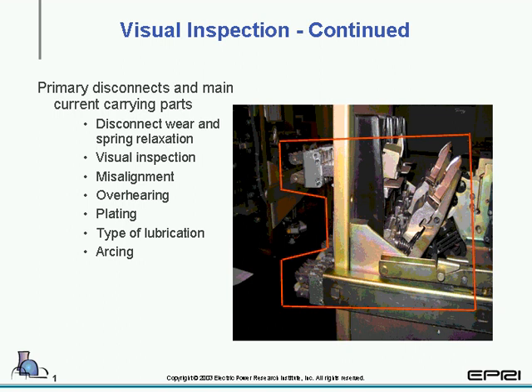So next we're going to take a look at primary disconnects and main current carrying parts. We're going to be looking at this later on as well. But when you're doing your preventative maintenance, what you're looking for is the list shown. Some of the most common are overheating and plating loss. Also, the condition of the contacts, and we'll be talking about that later as well. But as a general rule, these are some of the items you're going to want to do with your PM for your contacts.